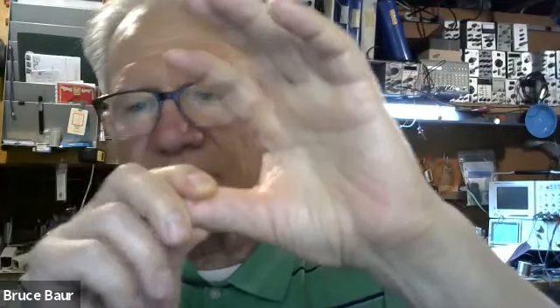You're not purely isolated, because you can have some noise on the line that's going to go across, and there is capacitive coupling there, so you will have some AC current that's common mode there. So if you tie one to ground, you'll get a little bit of current, or if you touch it with your finger. But it's kind of like a capacitor you might see from line to chassis as far as the current it would present - pretty minimal, not going to kill you, it's almost negligible.